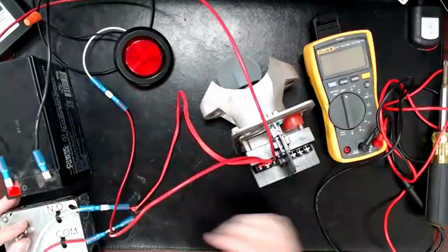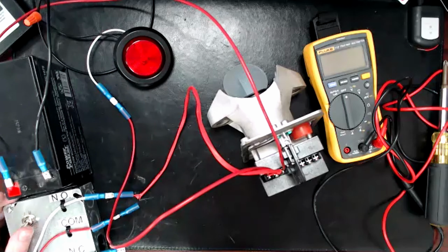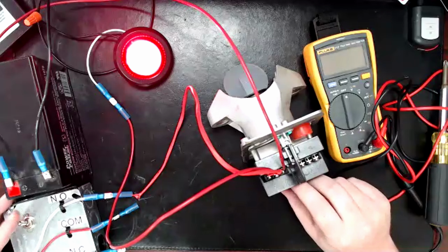So then if I take this here, you can see this one is able to turn that switch on and off, or this one's able to turn that on and off. So this switch is acting as a second water flow switch. I just don't have two of these to wire the two together. But I'm using the normally open and the common terminal here and the normally open and the common terminal here. And it's just jumpering common to common and normally open to normally open. And then either one goes off, it activates it. And then if both go off, you have a really bad fire in the building and it still activates.